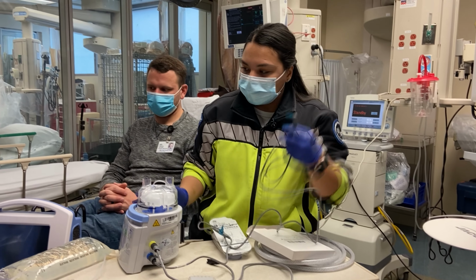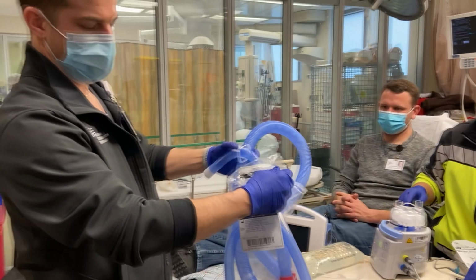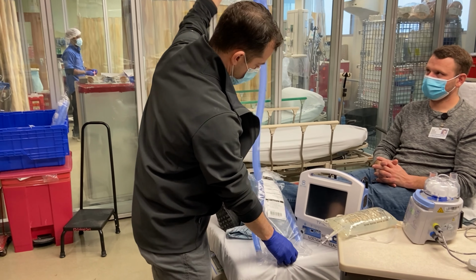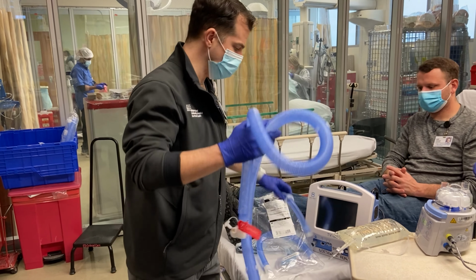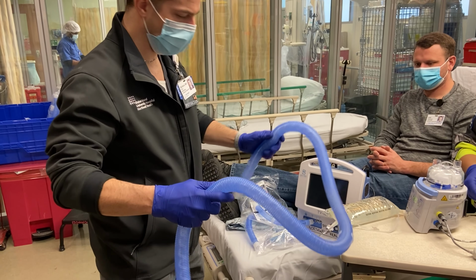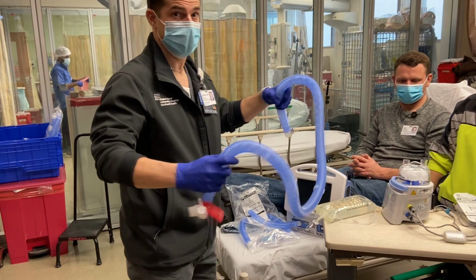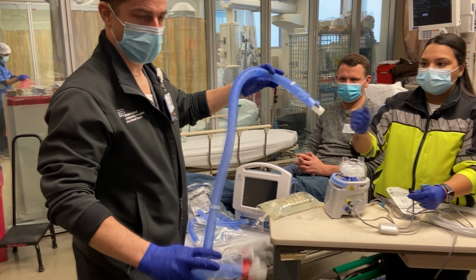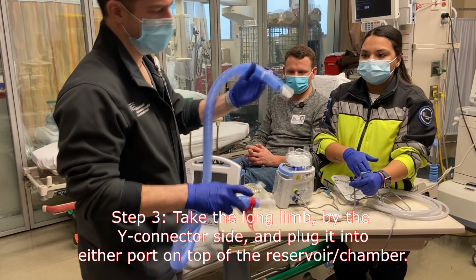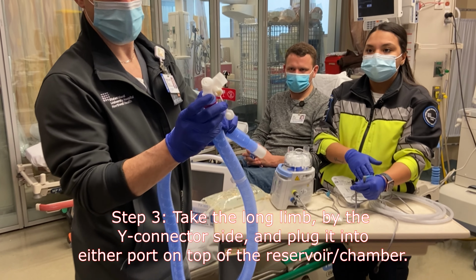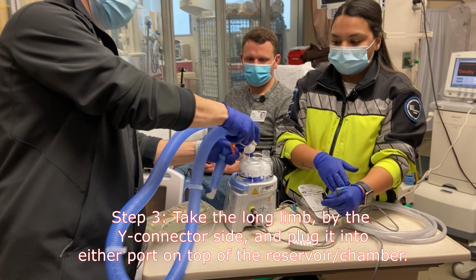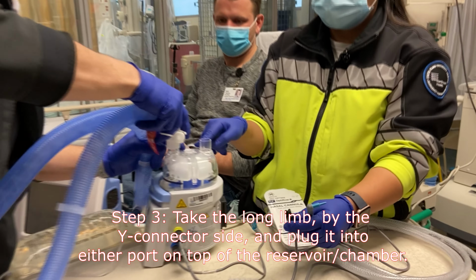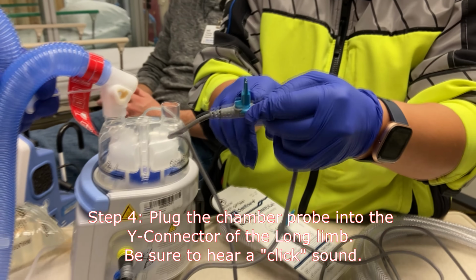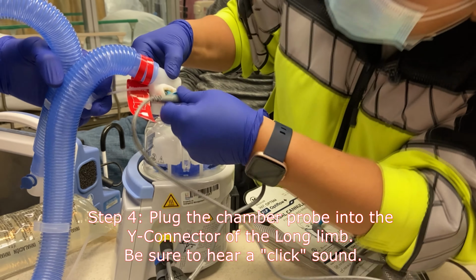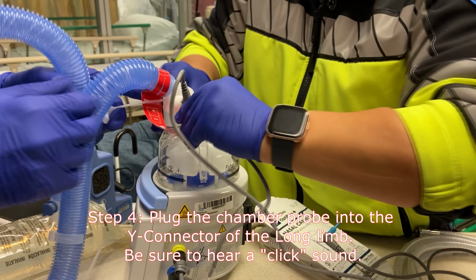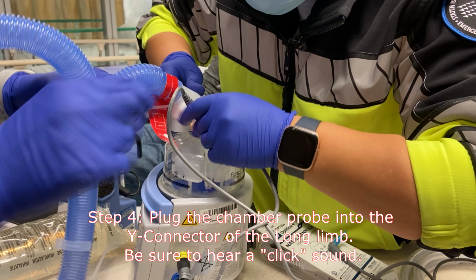To continue the setup, we're going to reach into our remaining circuit bag and take out the long limb first. There's 3 limbs, a long, a medium, and a short. The short limb does not need to be used. The medium limb is preferable, so we're going to start with the long limb. The Y connector here is going to connect to either of these ports. So this sensor here will go into this prong over here, twist, and push. And a click. Wait, hold on, it's not, you got it. Oh, there we go, okay.